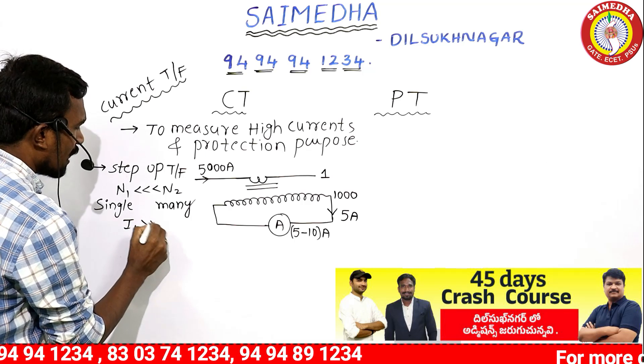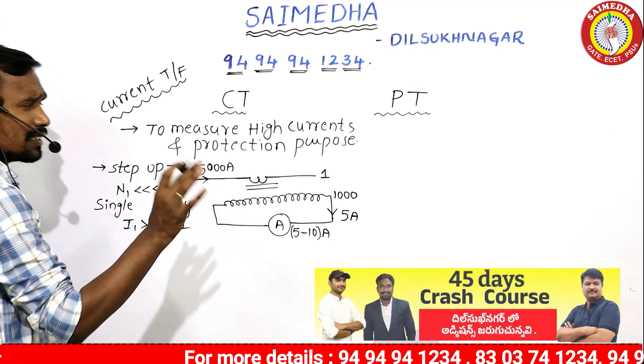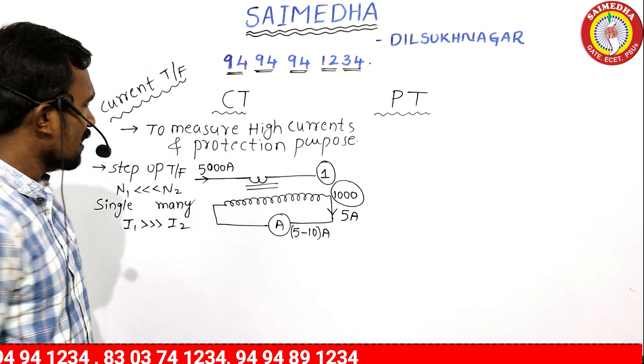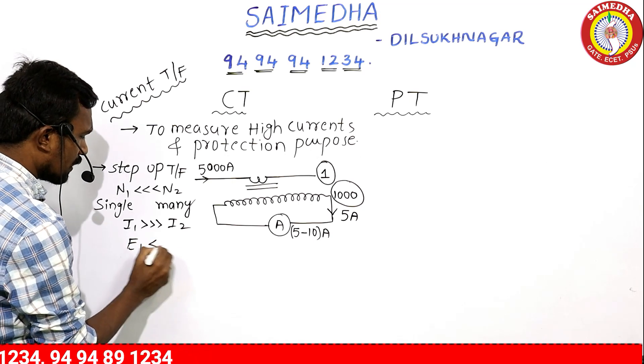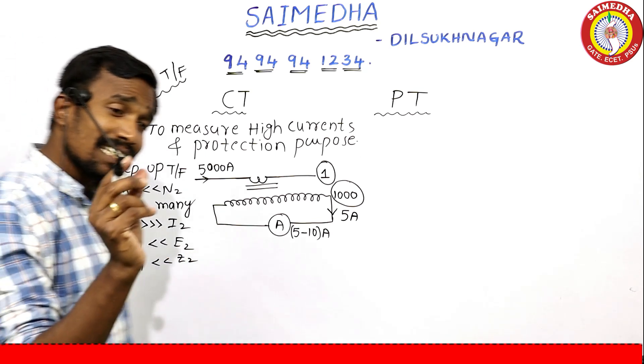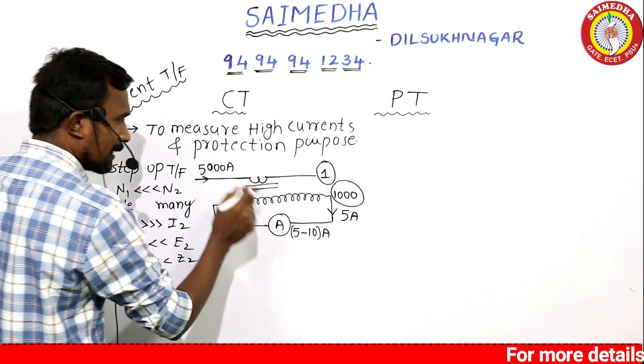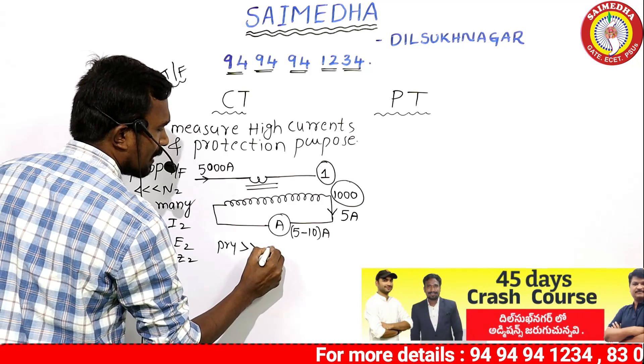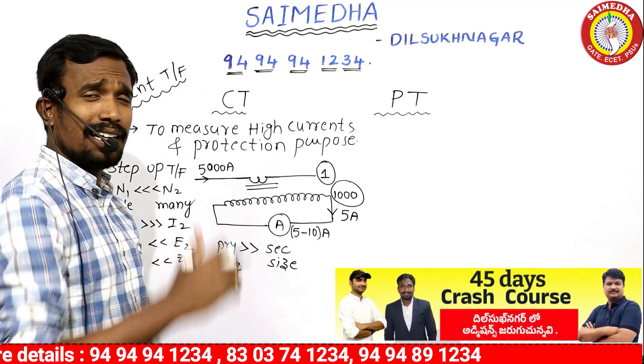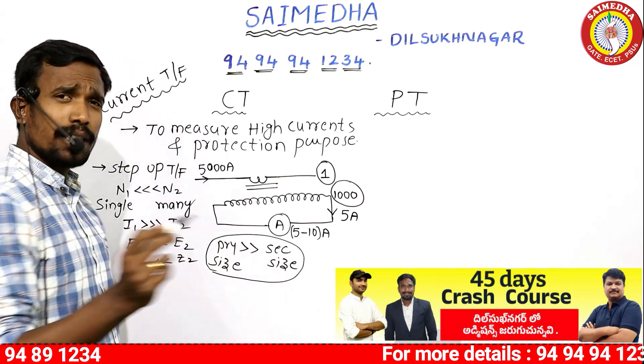The primary current I1 is very high, but the secondary current I2 is very low. The CT is a step-up transformer: primary has a single turn, secondary has many turns. So E2 is greater than E1, and Z2 is greater than Z1. The conductor size of the primary must be larger, as it carries high current, while the secondary conductor is smaller.